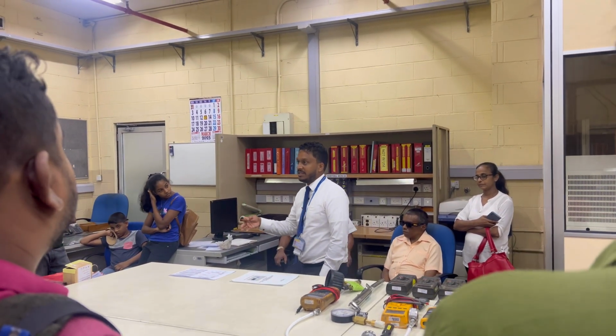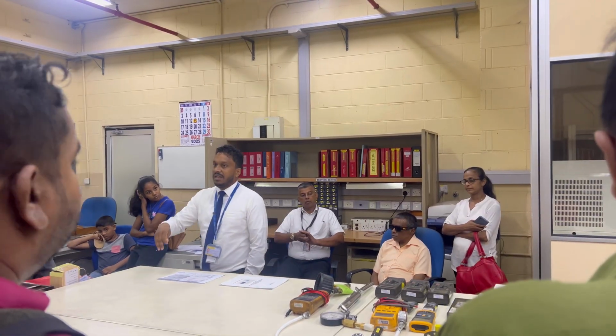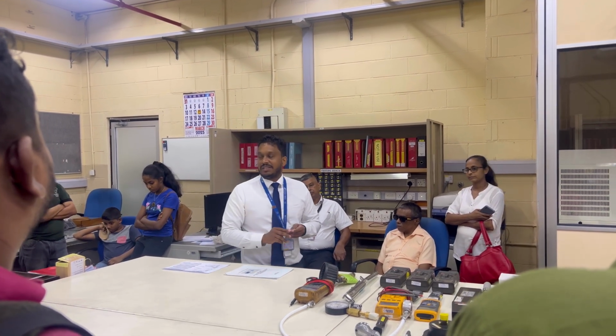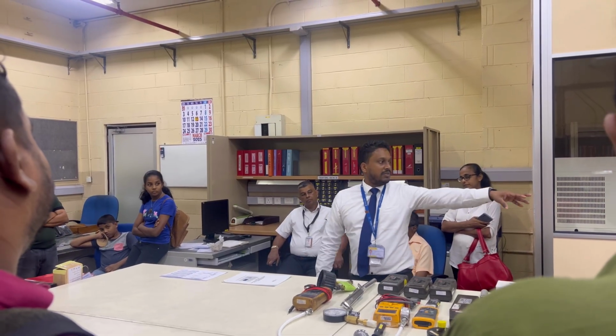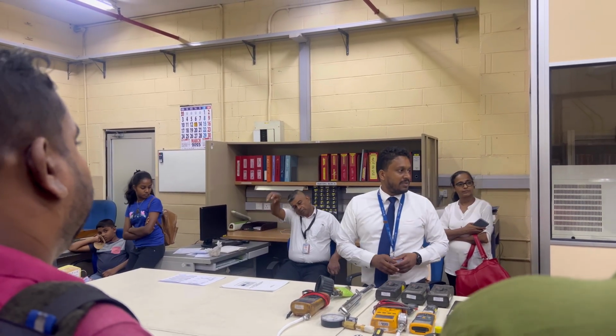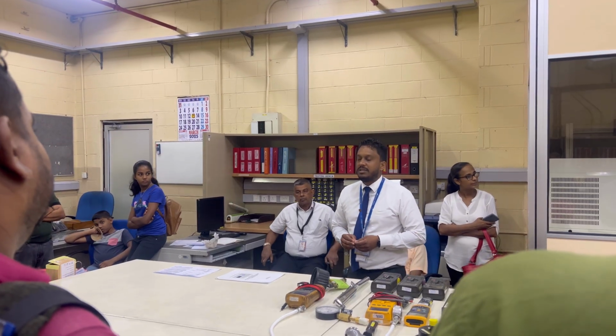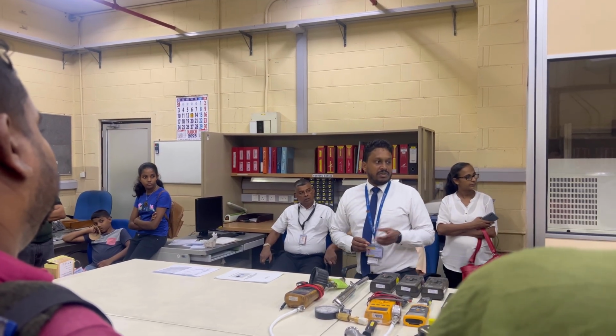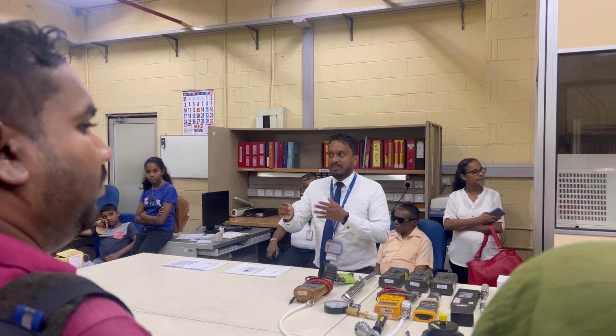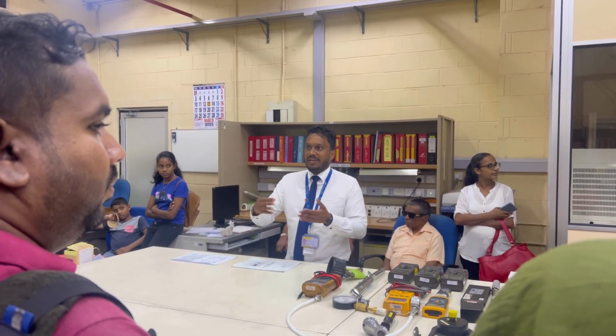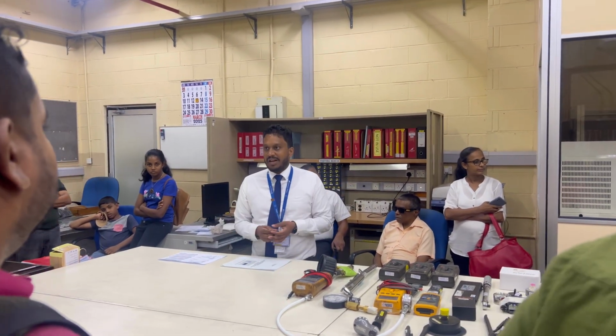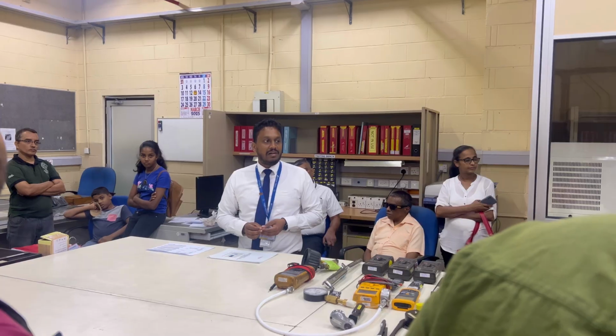We went for accreditation in 2019. We are one of the laboratories in Sri Lanka that are accredited because torque wrenches are not actually required by the authorities to be calibrated by an accredited facility. Yeah, they do torque checkers, and so we actually went and bought this equipment specifically for torque wrench calibration. So our laboratory was the first to get that. We had some problems doing some inter-laboratory comparisons, because there are no laboratories in Sri Lanka accredited for that.